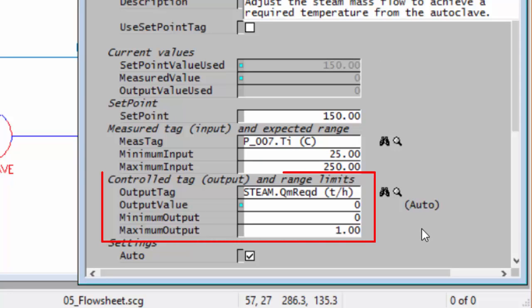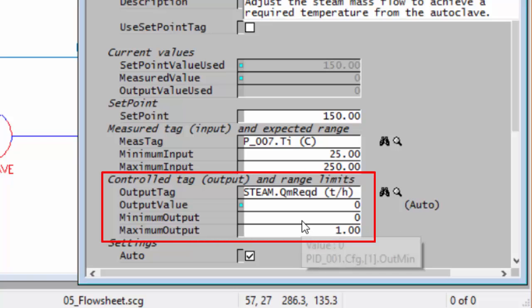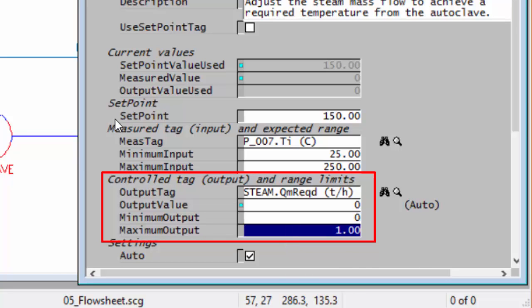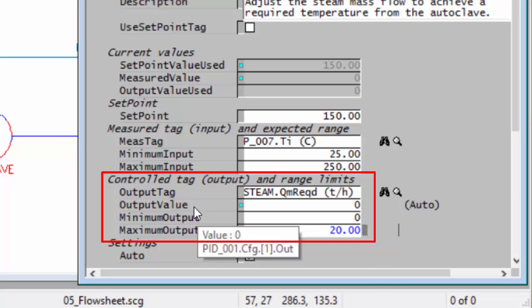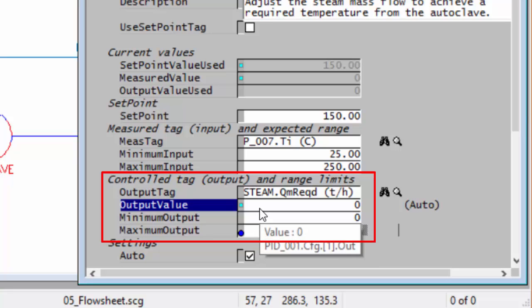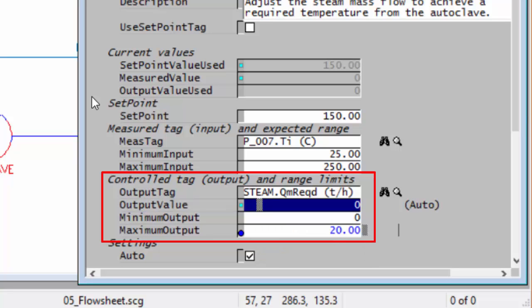Then our output, how much steam do we think we'll need? Well we'll leave it as a minimum of zero and the maximum let's say 20 tons per hour of steam. The other thing you can now fill in, it's also optional, is you can give your controller a starting output value and this is actually quite useful for when you're setting this up. We have our steam at five tons an hour so let's get it to start at five tons. So there we are.